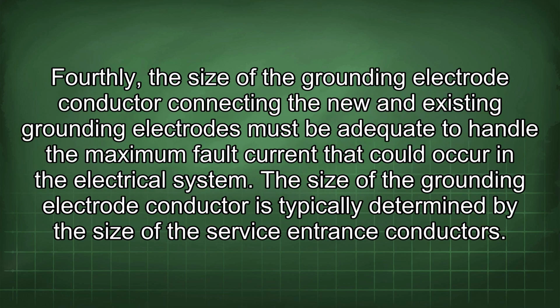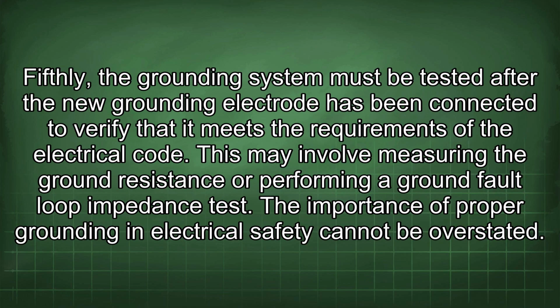Fourthly, the size of the grounding electrode conductor connecting the new and existing grounding electrodes must be adequate to handle the maximum fault current that could occur in the electrical system. The size of the grounding electrode conductor is typically determined by the size of the service entrance conductors. Fifthly, the grounding system must be tested after the new grounding electrode has been connected to verify that it meets the requirements of the electrical code. This may involve measuring the ground resistance or performing a ground fault loop impedance test.